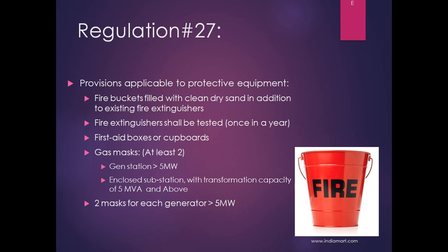There are incidents in the industry where every system is in its place, but when the actual requirement came, they didn't work. To avoid such a problem, you should have a fail-proof system like fire buckets filled with sand. You put that sand on and over the electrical fire, that will extinguish the fire. Also, the fire extinguishers shall be tested at least once in a year. First aid boxes and cupboards shall be installed. Gas masks shall be present. At least 2 gas masks shall be present for generating stations of more than 5 megawatt capacity, and enclosed substations which have transformation capacity of 5 MVA and above.